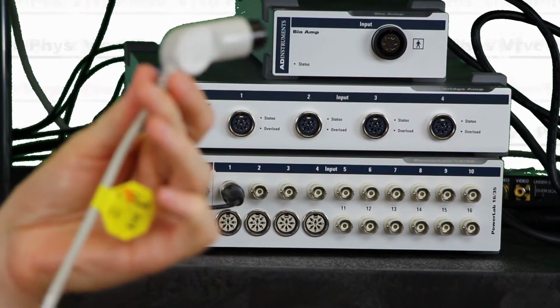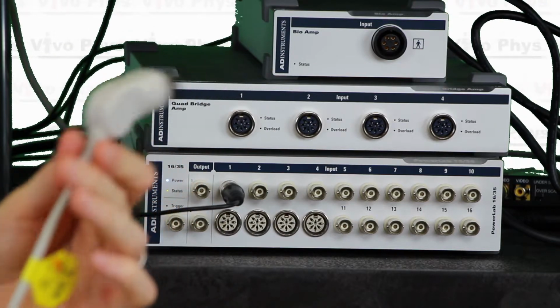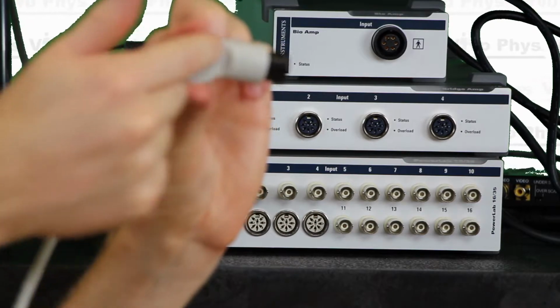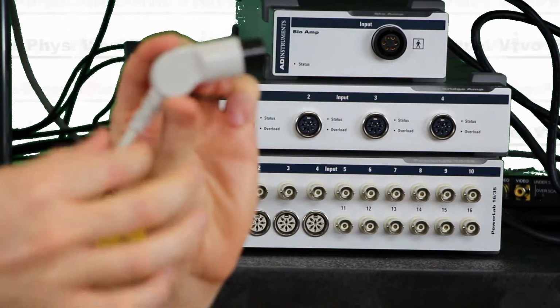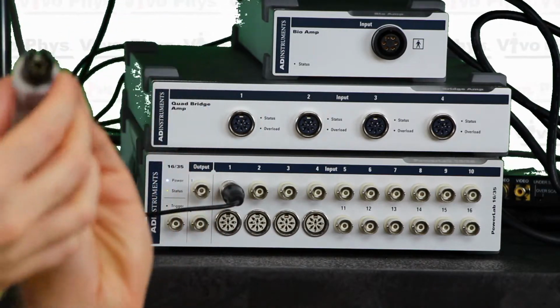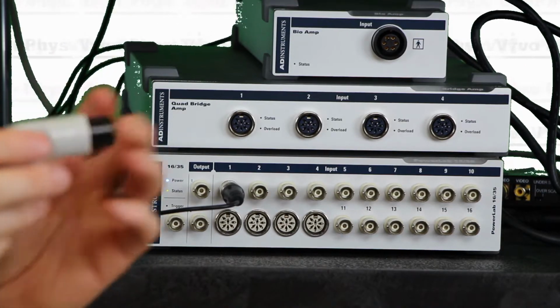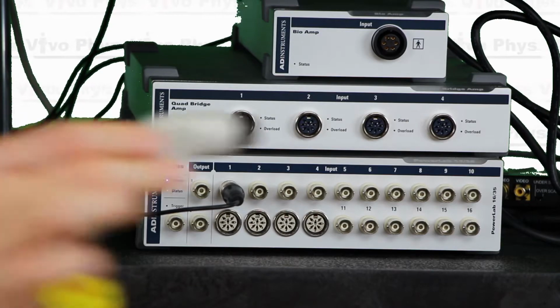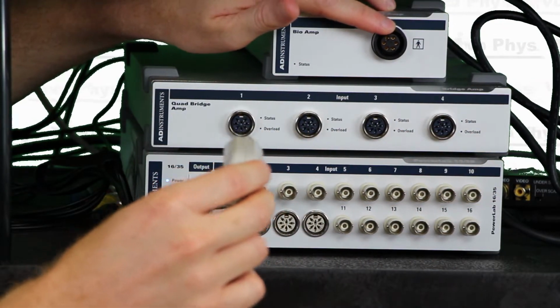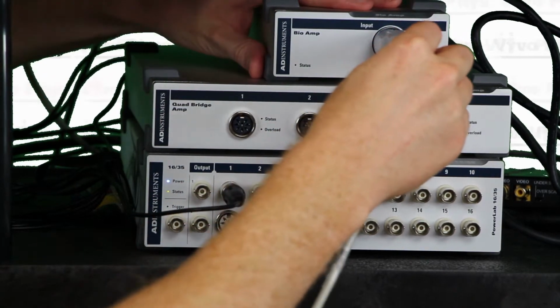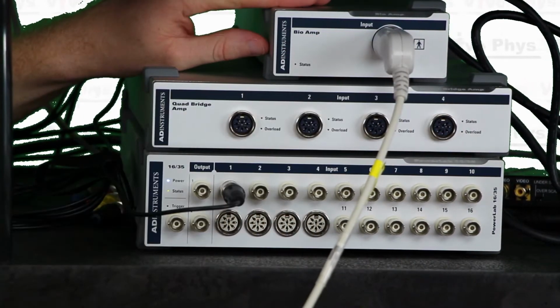All right, so here are the ECG electrodes. They're connected to the bioamp that's connected to the PowerLab by this cord here. And so what I'm going to do is plug this in. If you look at it, it's got a weird shape to it. You want the cord coming to the bottom here, not coming upwards like that. And there's a little slot right on the top-hand side that's going to tell you where the top is. So that is going to get plugged into the only port on the top of the front of the bioamp. Just push it right in, it goes in firmly, and now everything is connected.